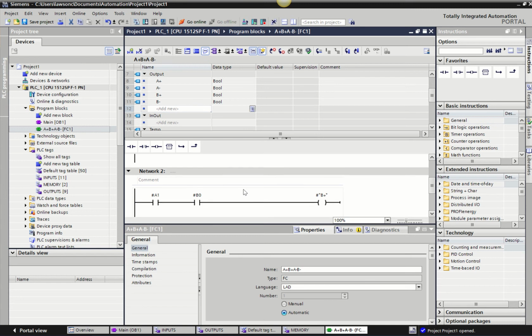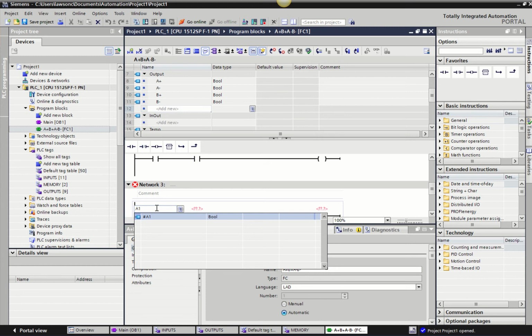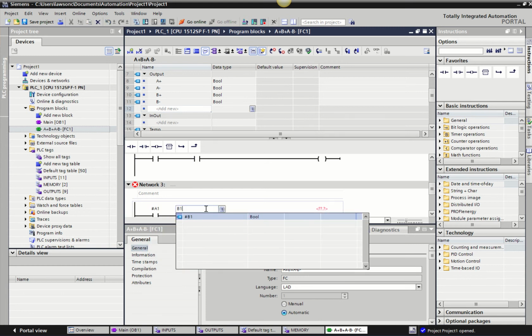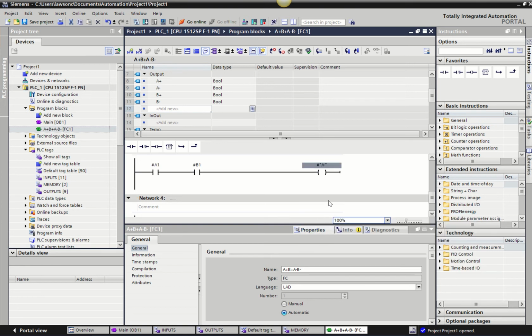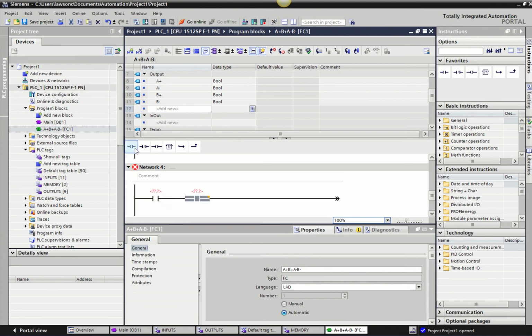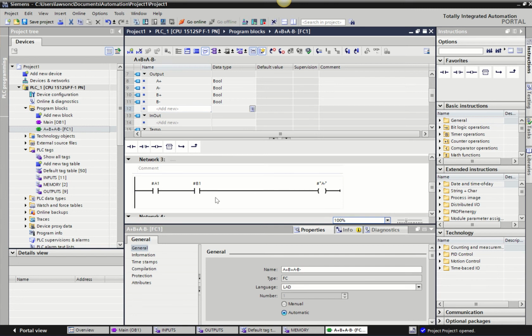I'm going to have a similar setup again down here. Again, two inputs, going to trigger an output. So B has gone out, A is extended, and B is now extended. So we want A to go back in. And then finally, A has now returned home, and B is still extended, so we want B to come on home now. So that's just me setting up my sequence, okay? A goes positive, then B goes positive, then A goes minus, and B goes minus. So that's my function, okay?